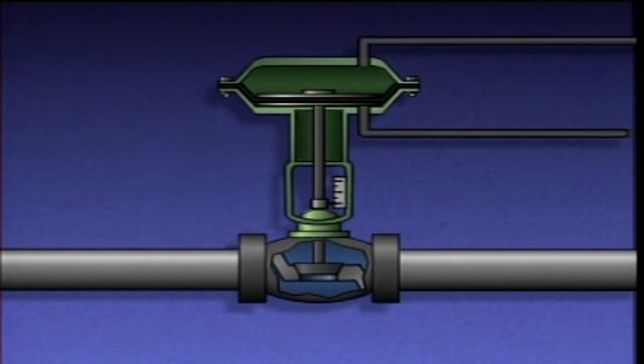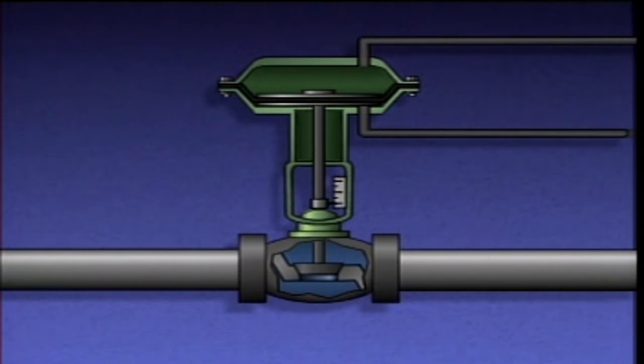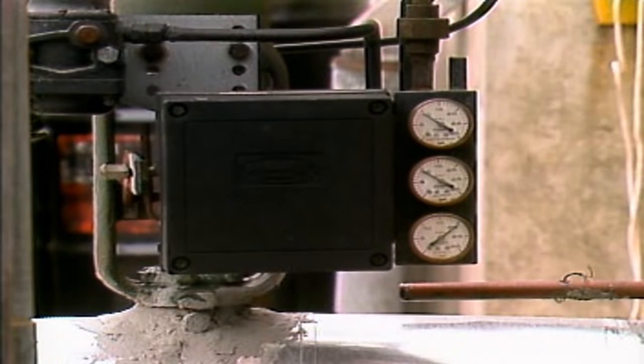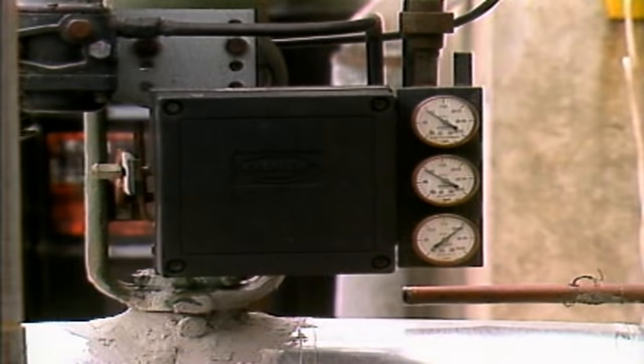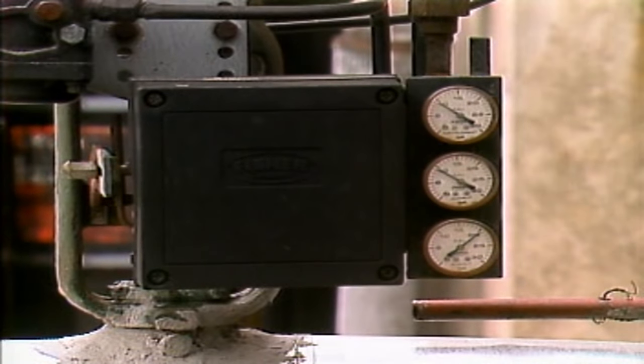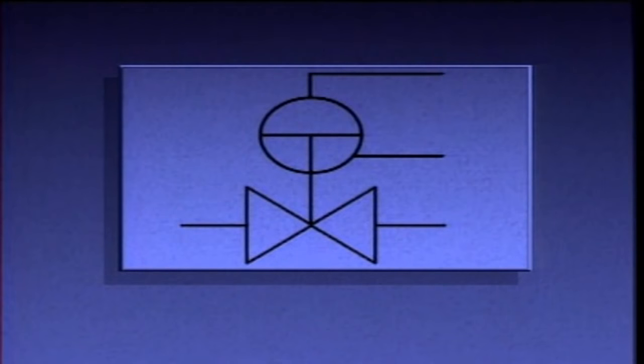Controlling the applied pressures enables the actuator to position the valve anywhere within the limits of travel. In most applications, accurate positioning is achieved by using a device such as a positioner to add air to one side of the diaphragm and bleed it off the other side.